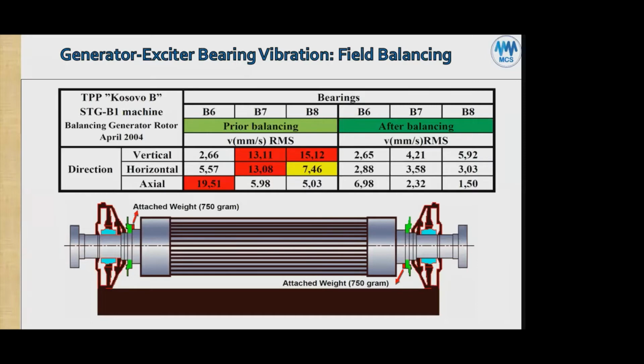It should be that a rotor, as it vibrates, does not cause any destructive damage to the machine, meaning no babbitt impacting, no babbitt fatigue in the bearings, no fatiguing of the bearing housing supports, and no fatiguing of smaller bore piping connected to the turbine. All of these end up as damaging vibration. Whereas when you have a smoother vibration, which we call acceptable limits, the machine can run for years and it hasn't damaged the bearing or the supports or anything connected to it.